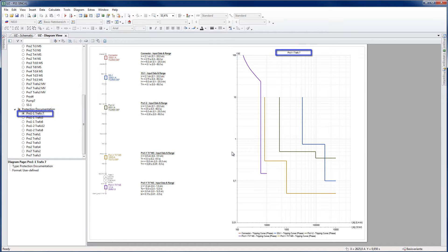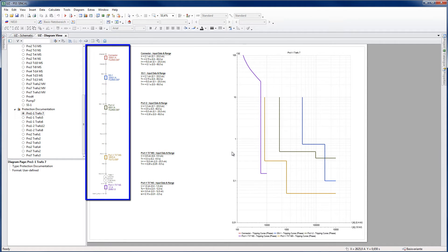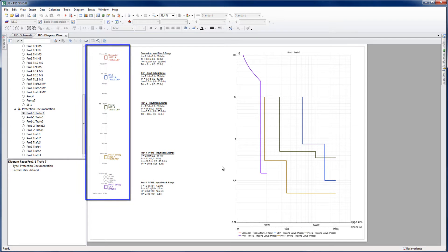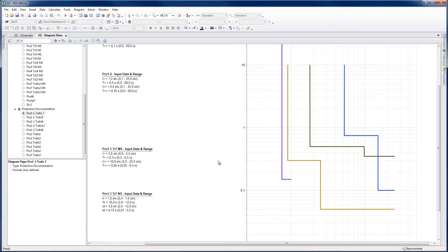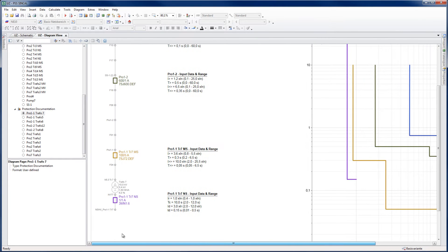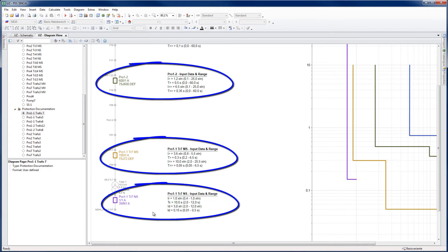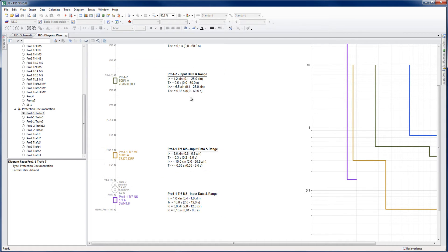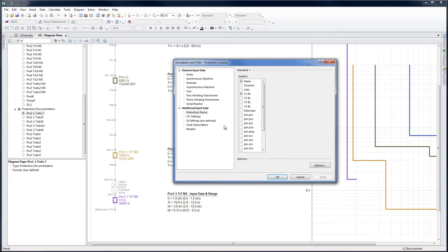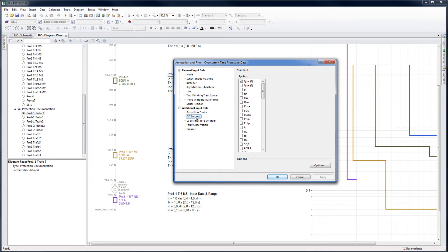The selected protection path is now shown on the left with all network elements that were in the path. Selected data is shown for the elements and detailed information is shown for the protection devices, including current settings and acceptable setting ranges. The amount of data shown and in what format can be selected by the user through the usual filter and annotation menu.